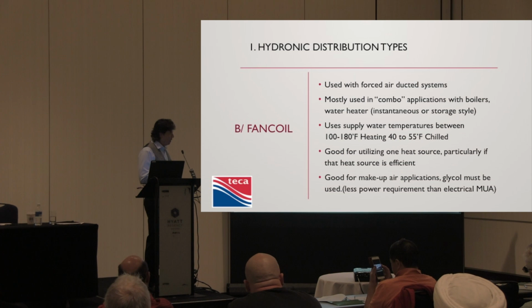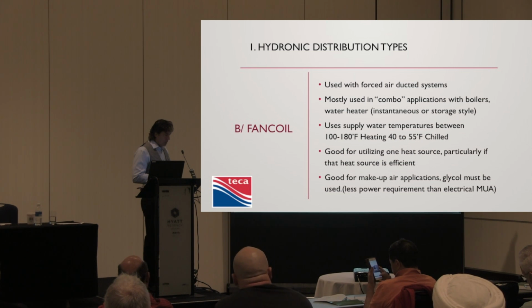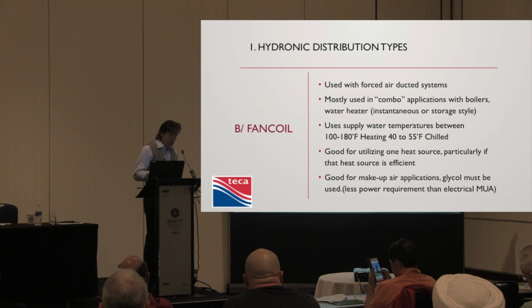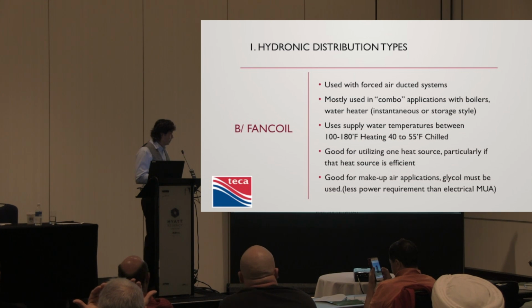And why not put chilled water through them if you happen to have a heat pump that reverses the cycle, and now it's providing cold water instead of hot water? You've got a fan coil, so why not have chilled water go through there? Now we've got air conditioning. So like I say, you could have, let's say, a combi boiler, do a little bit of radiant, do your domestic water, and set up a fan coil to do just straight ahead forced air in whatever zone you want to choose. It's also good for makeup air applications.